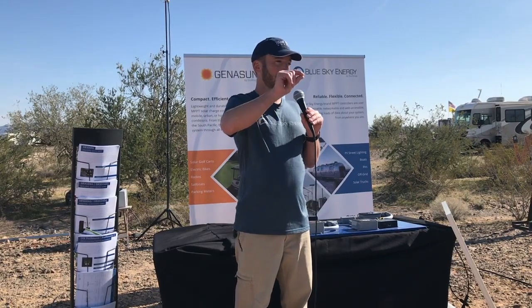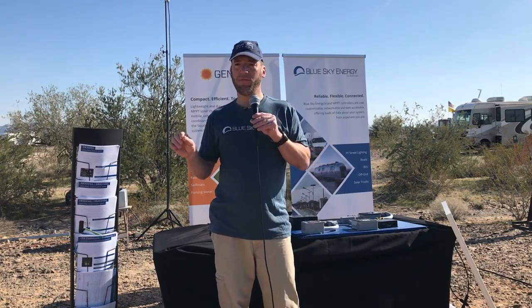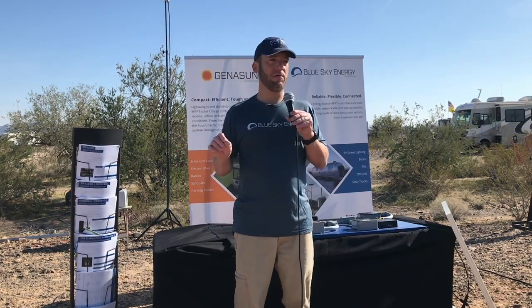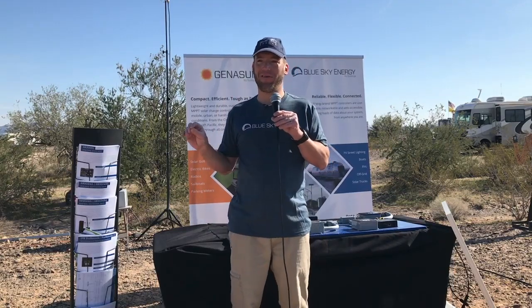One of my nemeses in product support is the flexible bladed fuse holder - the wiggly wire, plastic box type. I'm not saying they're all bad, but over the last 3-4 years doing this job, 1 to 2 times a month I've had a bad fuse holder issue for a customer - not the fuse itself going bad, but the holder. Some brands make good ones, like Blue Sea and Littelfuse. But the majority of AutoZone, Radio Shack-type fuses that you think are good - no, no, no. They fail, and they fail in a way that's hard to detect, sometimes causing voltage drop, sometimes just stopping working.